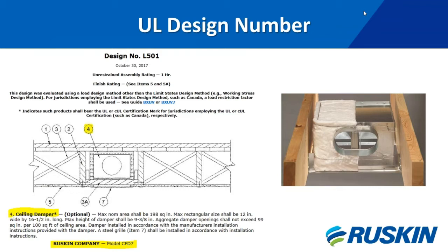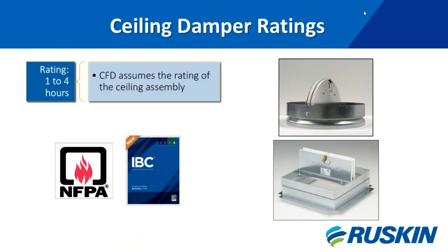Once the damper passes the fire test, the manufacturer's damper model can be added to the design, or a new ceiling design number will be assigned for that product. Ceiling dampers can have a fire resistance rating from one hour up to four hours depending upon the structure they are installed in. Wood joist and wood truss assemblies only have a one-hour fire resistance rating.